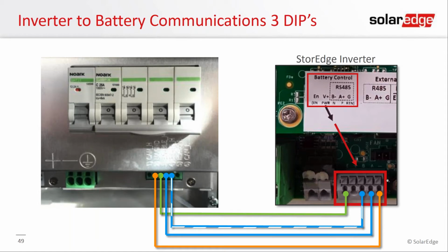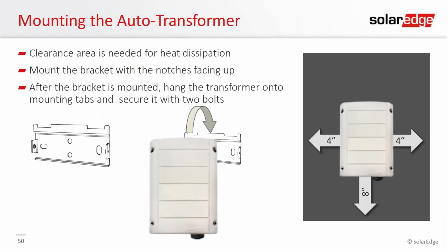So you just use your flat blade screwdriver, push that open, put your conductor in, and then give it a little light tug test to make sure it's seated properly. The autotransformer, that's pretty heavy. It's a pretty solid chunk of copper, essentially, because transformers are copper. So it's misleading how heavy it is. I've seen a lot of guys accidentally drop it or not expect it to be as heavy as it is. So make sure you handle with care.